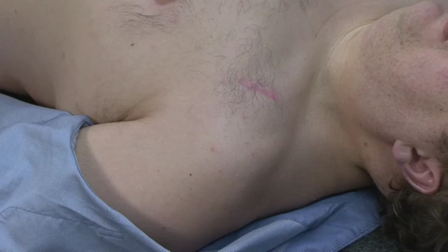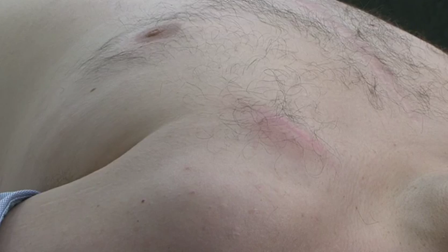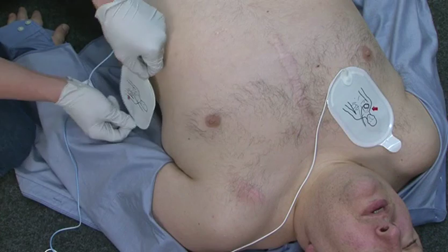Someone may have a surgically implanted device in the chest, such as a pacemaker or an automated internal defibrillator. A noticeable lump and surgical scar will be visible. If the implanted device is in the way of correct pad placement, place the pads so the edges are at least 1 inch away from the device.